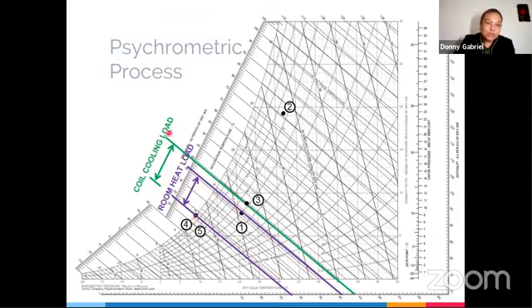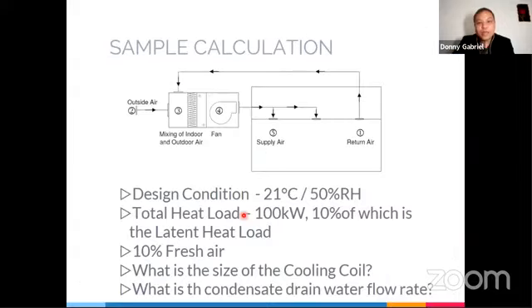So this is your coil load, the green one, and the purple one is your room heat load. So you can see back on our schematic, no? In our schematic, this coil load now is 90% of this one and 10% of this one. Earlier it is 100% of this one and 0 of this one. But now you have 90% of this and 10% of this. So which means your coil load is significantly lower, very much lower.